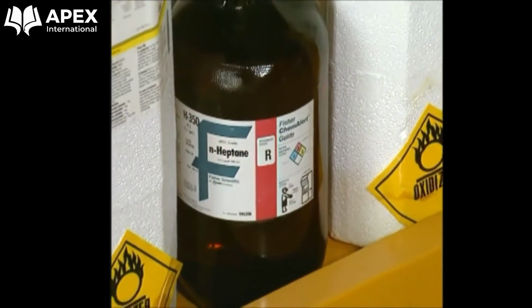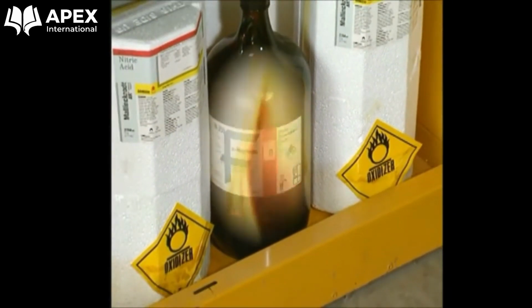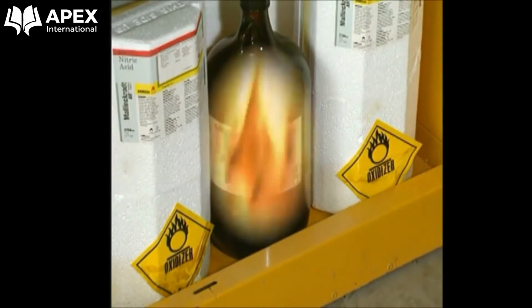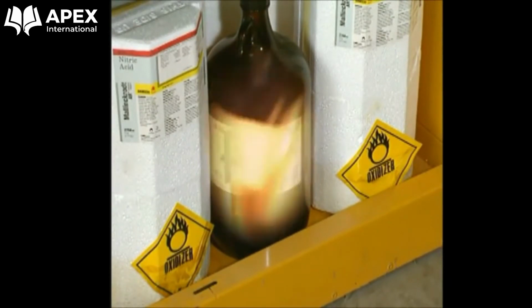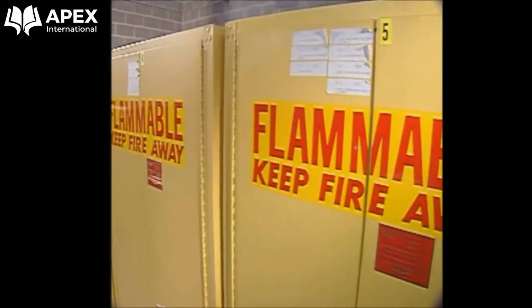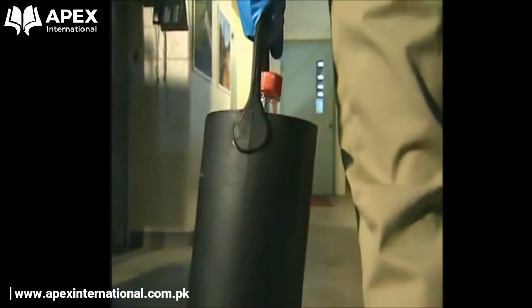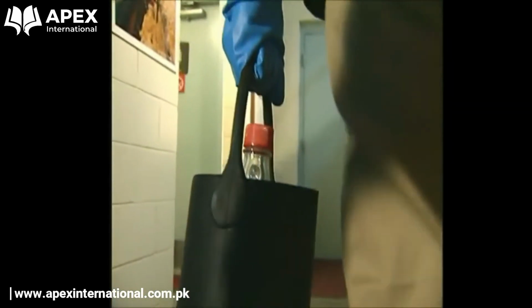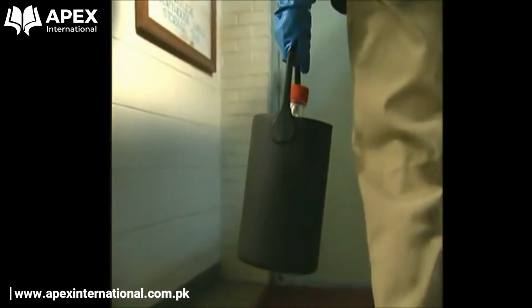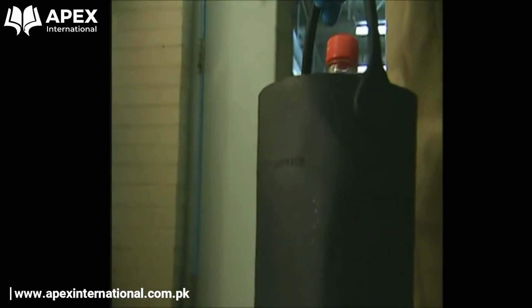Oxidizers and flammables are a dangerous combination. Store them well away from each other to prevent violent reactions in case of fire. Use NFPA-approved fireproof cabinets to store flammable materials away from the work area. Many accidents occur when chemicals are being moved to and from storage areas, so use common sense and the methods your facility has outlined when moving hazardous chemicals. When working with any hazardous chemical, keep the area well ventilated to prevent harmful vapors or dust from accumulating in the air.